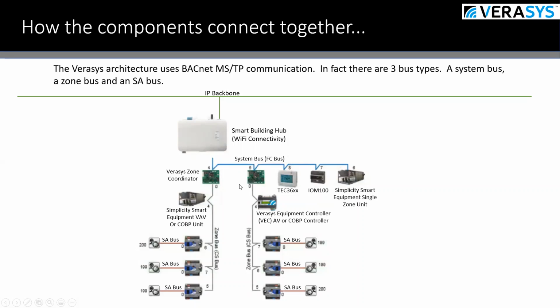But with this bus structure and zoning, this zone bus here allows us to do even more, because the coordinator picks up the equipment and all the zones. It's its own little separate network. And remember, these zones are all getting fed into the coordinator, which is telling the rooftop what to do. So just for reference, you can have 10 of these zone coordinators on your MSTP bus, and underneath those, you can have 32 devices. So now we're talking about more than 300 devices on the network with just those 10 zone coordinators. This is pretty powerful, and it really opens up Verasys as an option for more complex facilities. And then the other bus here, your SA bus, is bringing the sensors into the controllers as well. This is exciting because it really does expand the system to become pretty substantial.